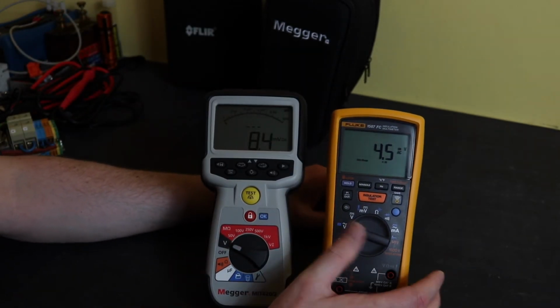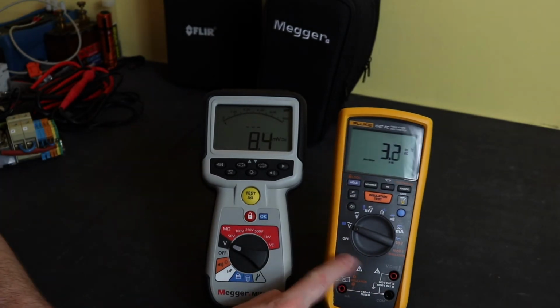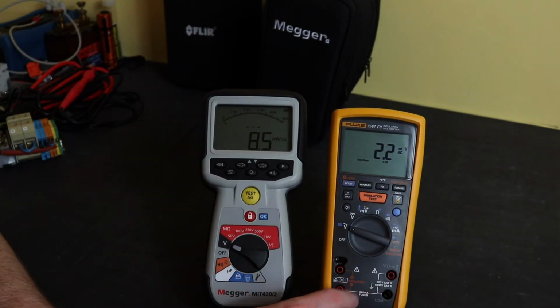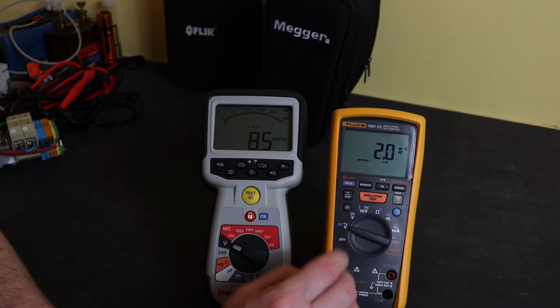In terms of the front of the meter here, 4 input jacks in the traditional position on a multimeter, I guess, volts, and then a common current, and then a common, and then the insulation test is from these 2 jacks here, the positive current and a special jack here just purely for insulation testing. That's the one I always mess up with. Every other insulation tester I have, or the vast majority, has a special jack, but it's always to the common. Fluke have totally fooled me by taking it to the positive current terminal. Throws me every single time.